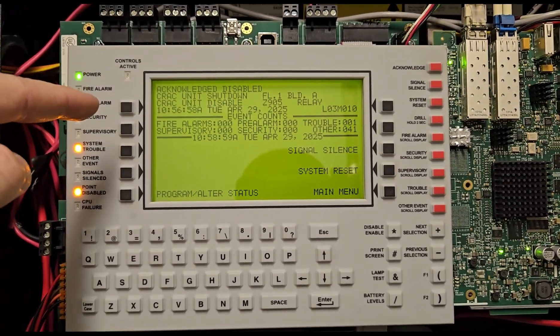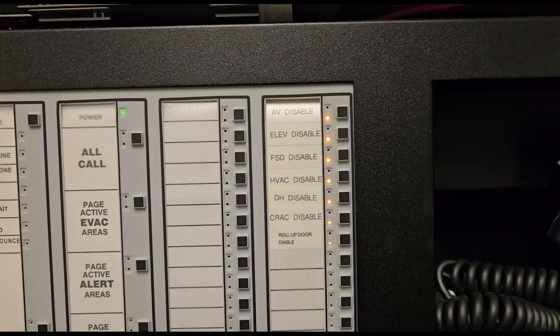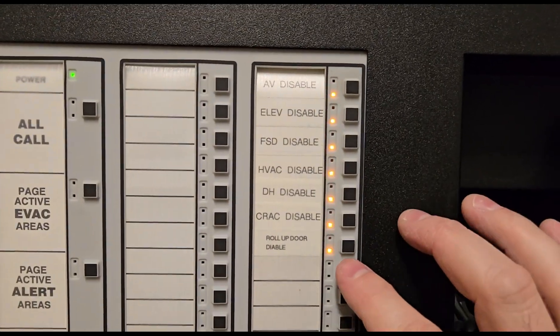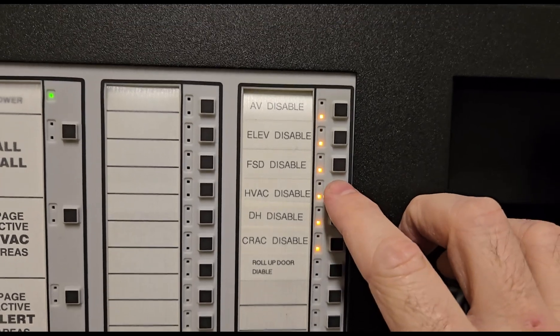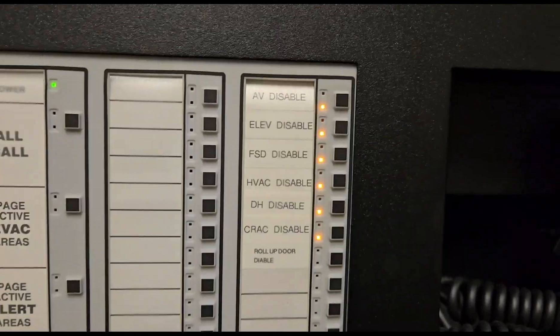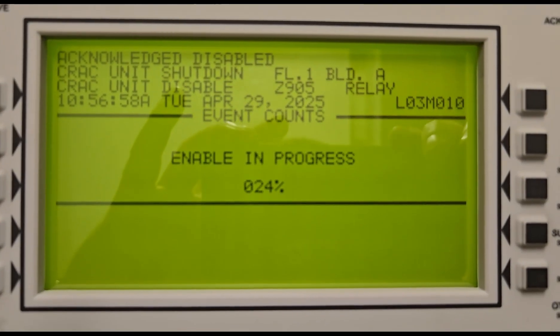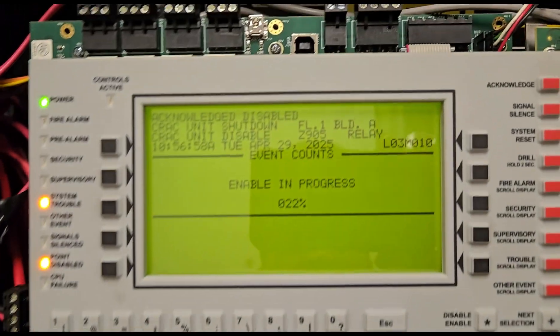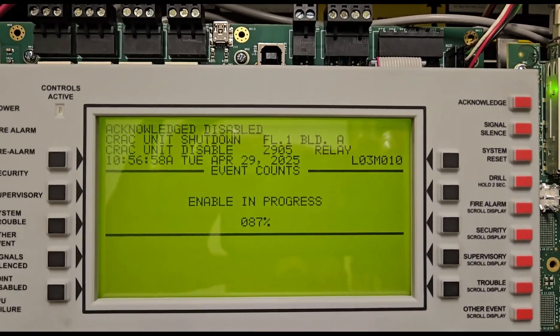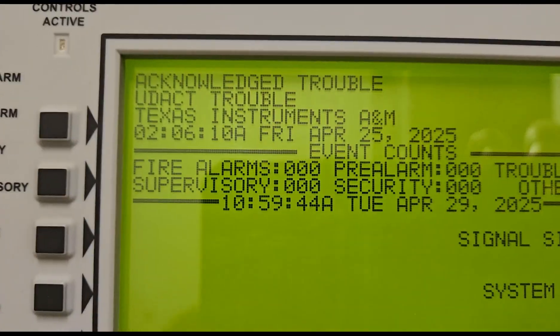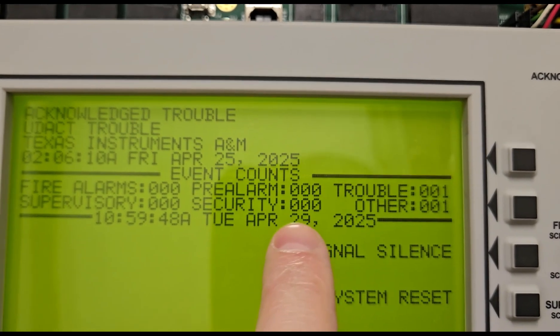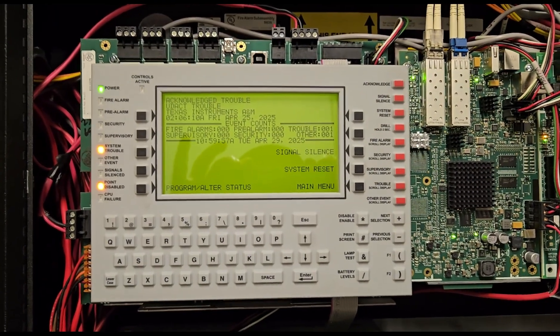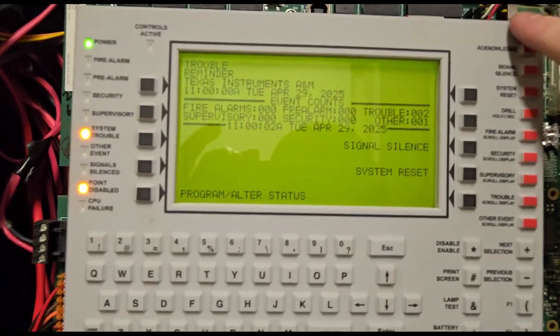You can now go through the system and test everything without any alarms or signals going off — everything still reports to the panel, these switches just won't activate anything. At the end of the day when you want to re-enable everything, reset your panel, make sure everything's clear of alarms, then go through the reverse process and enable everything. You just hit them all one time — the panel says 'enabling in progress' with a percentage counter as it works through all the disabled points.